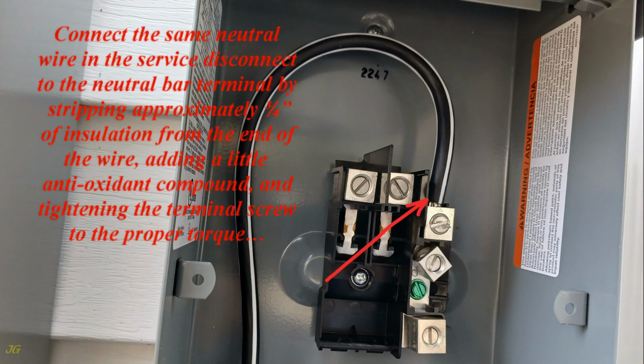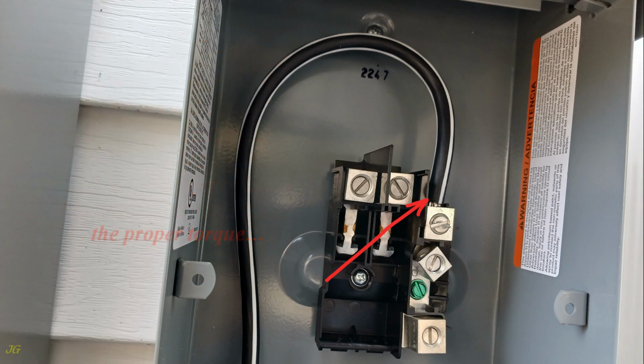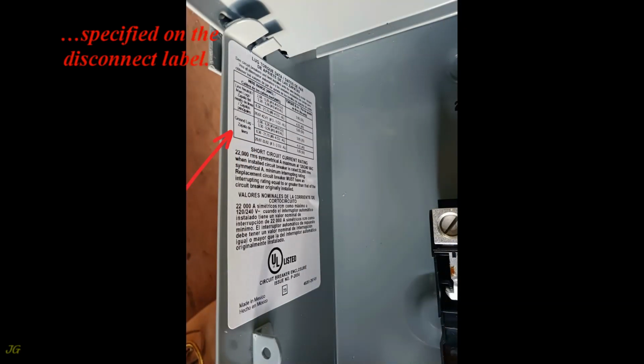Connect the same neutral wire in the service disconnect to the neutral bar terminal by stripping approximately 3/4 inch of insulation from the end of the wire, adding a little antioxidant compound, and tightening the terminal screw to the proper torque specified on the disconnect label.